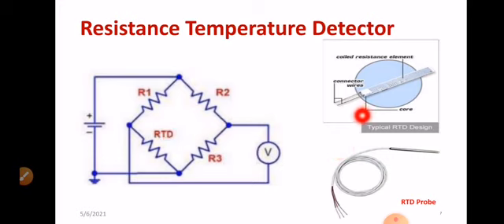So this is the way an RTD probe looks. So this is a typical RTD design. You are able to see. However, you can say that the platinum element, the resistive element, is the most important. And in this configuration, the calibration is also very important. And also how you are going to maintain the calibration matters a lot.